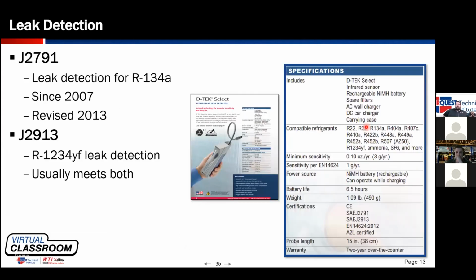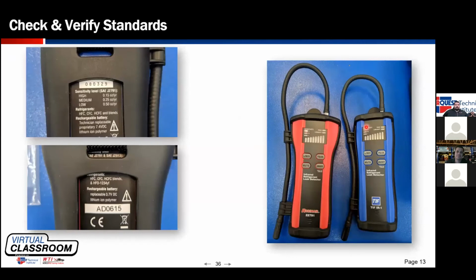Electronic leak detectors. Most guys have a love-hate relationship with electronic leak detectors. And we'll talk in the second part of the class more about electronic leak detection. Two standards for electronic leak detection, 2791 for 134A, 2913 for 1234YF. A 2913 leak detector generally exceeds the 2791 standard. What we are looking for, the standard, is that we can find a 4 gram per year refrigerant leak at a distance of 3/8 of an inch with the probe moving at a specified rate. So again, make sure that your leak detector meets these standards.